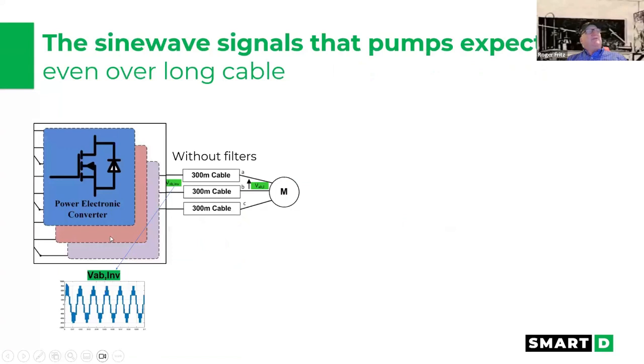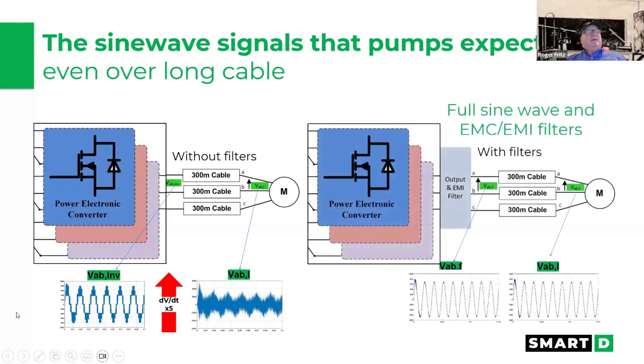The electronics are going out there. And we have no problem going long lead lengths, so you can see our comparison between the standard out there with those filters. This is the output with the dV/dt filter, and this is an output with this. So we have no problem. There's no peaky voltages, no EMI going out there. So the motor likes this. There's no fight going on between the motor and the drive.